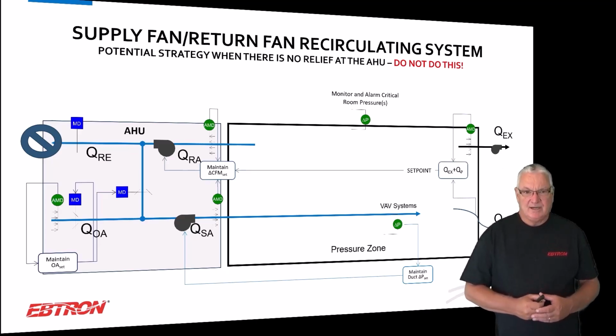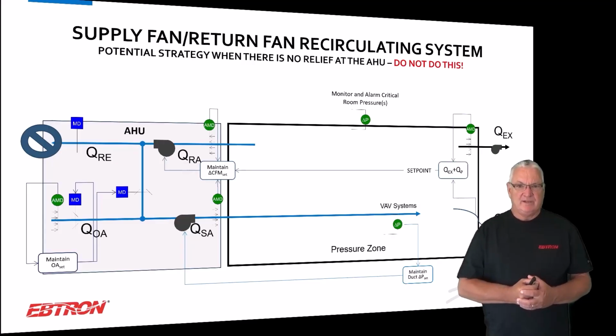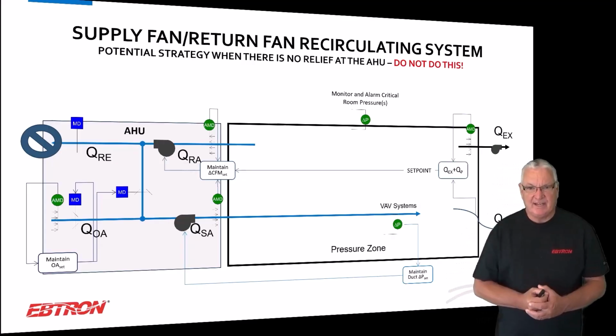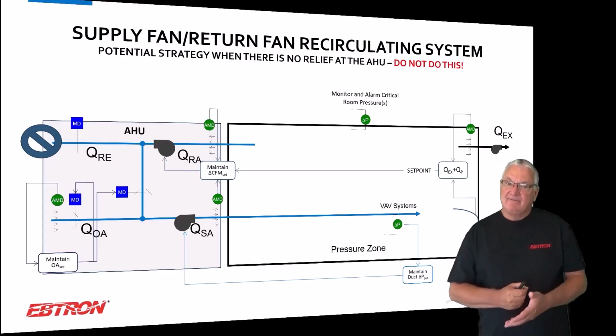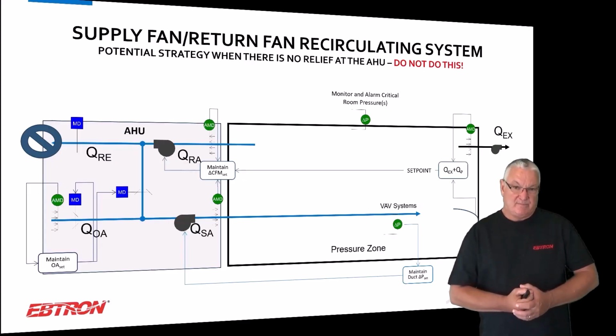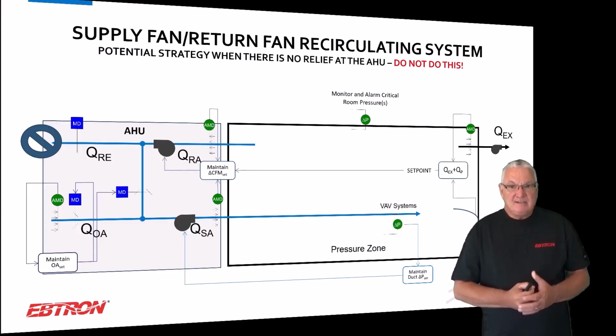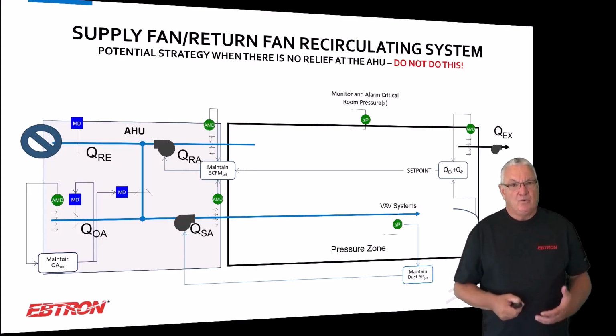I'm going to do supply minus return. I'm going to do fan tracking with my supply and return flow meters. I don't have any relief at the air handler. I may have exhaust in the space. Basically, you don't want to do this.